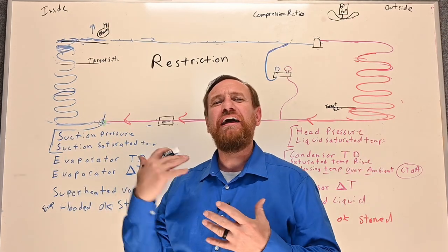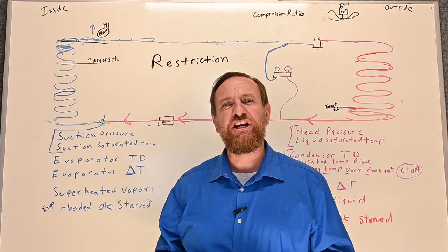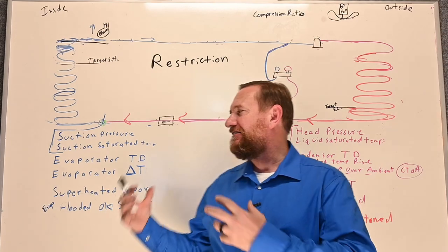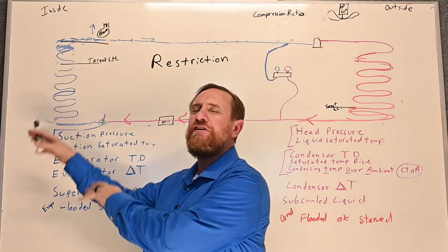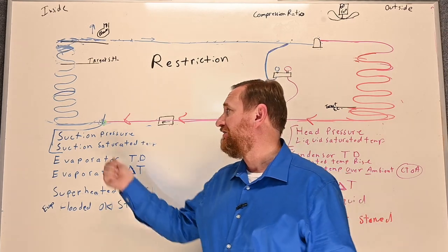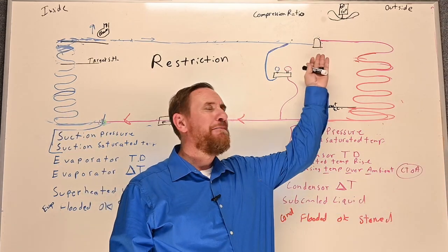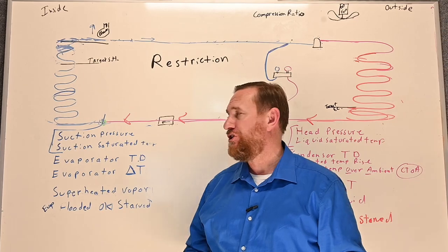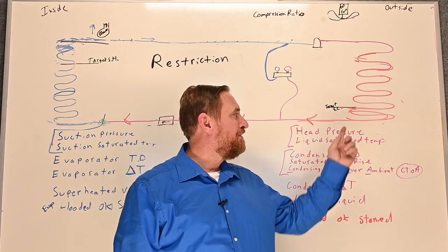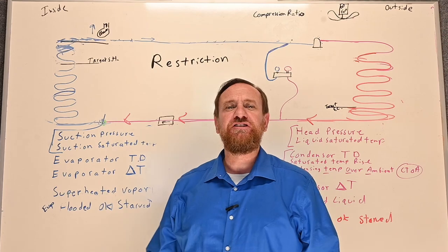Now that we understand a refrigeration cycle, let's apply another scenario: a refrigerant restriction. A refrigerant restriction means it's not flowing from the condenser to the evaporator like it should. There are multiple things that can cause refrigerant restrictions, such as the metering device being too small, a TXV stuck closed, a kink somewhere in the liquid line, a closed valve, or a clogged filter dryer.